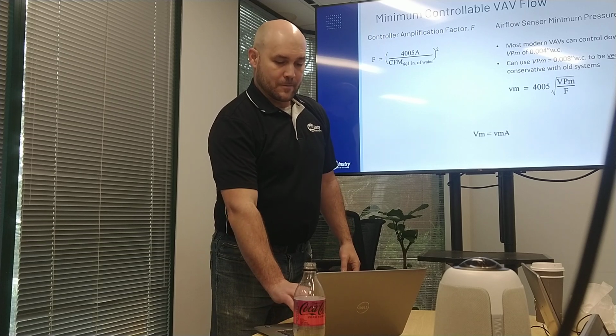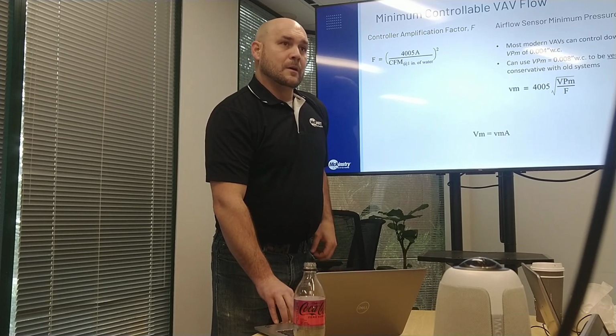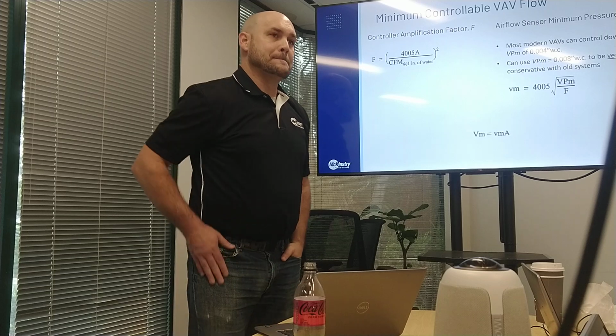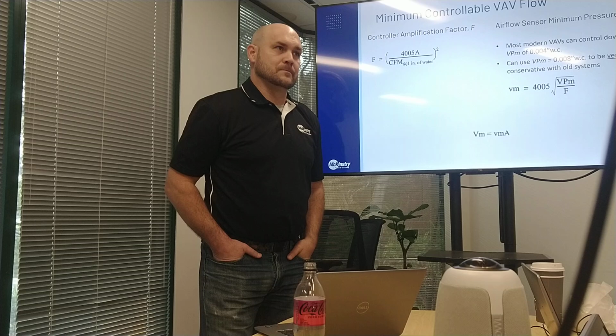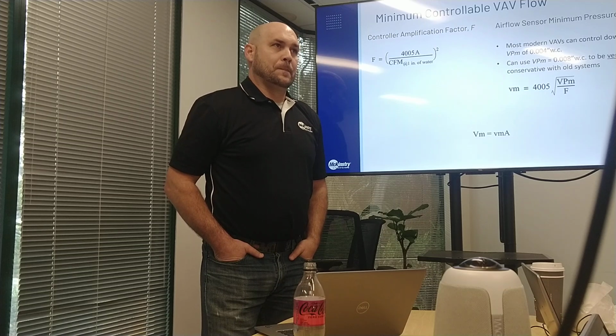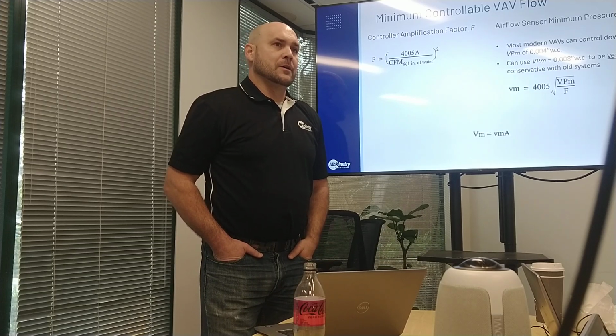James, how does that pressure at the box relate to the differential pressure that you're measuring at the air handling unit? There are obviously parameters that you want to stay within. You can't go down to 0 for a differential pressure reset. Right. But how does that minimum on a differential pressure reset relate to an individual box minimum?